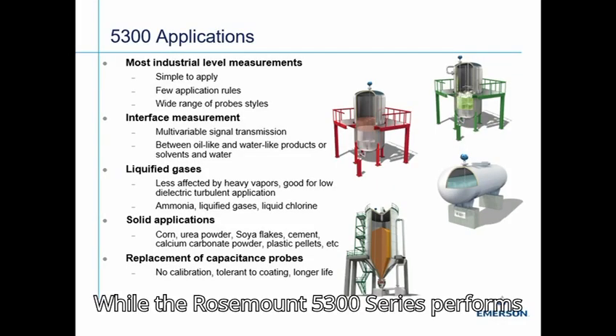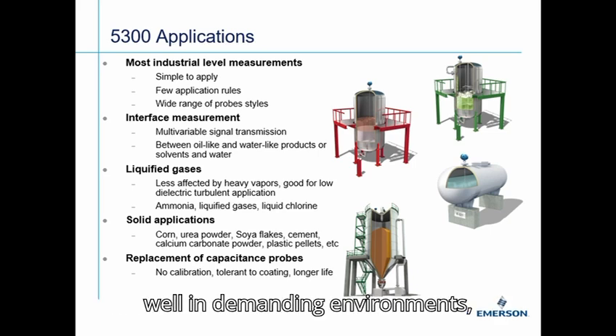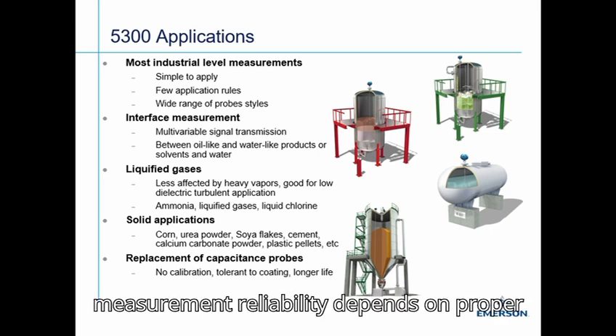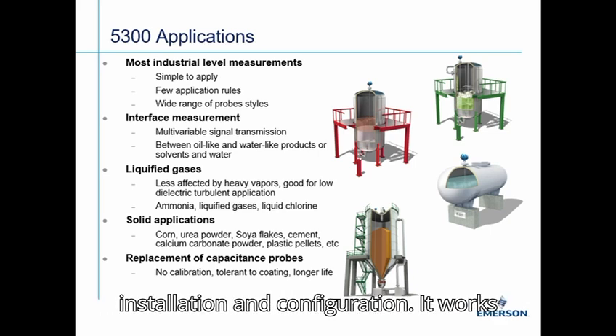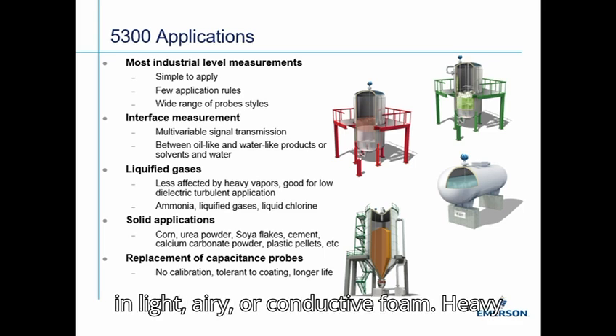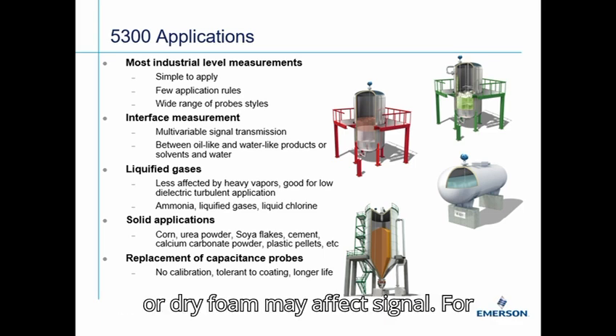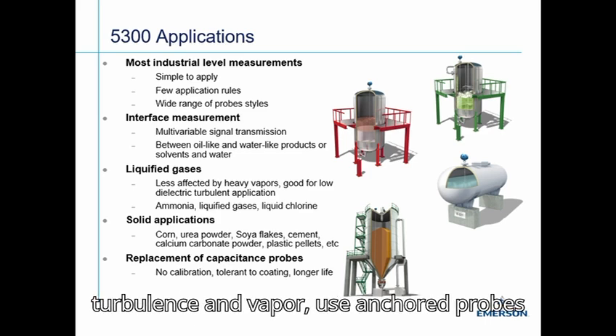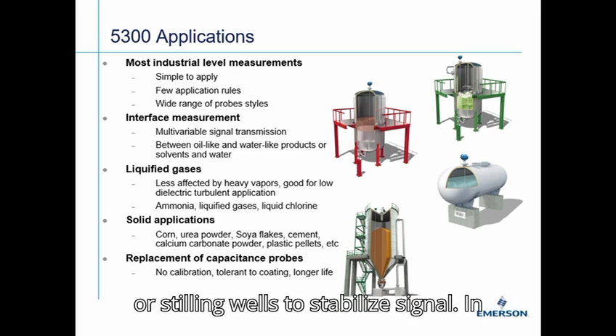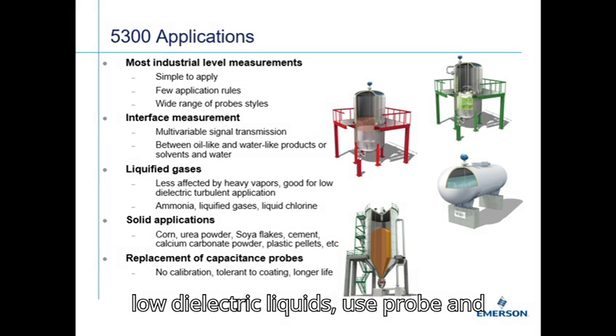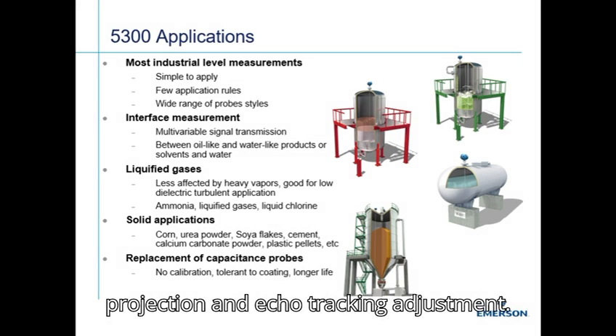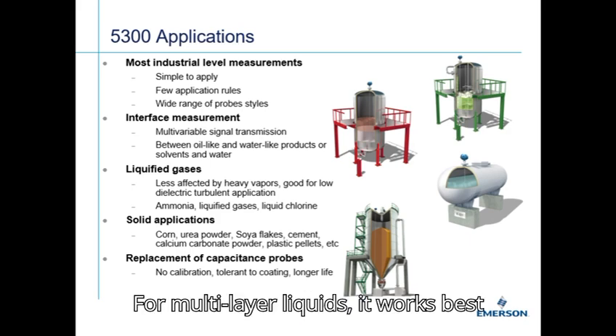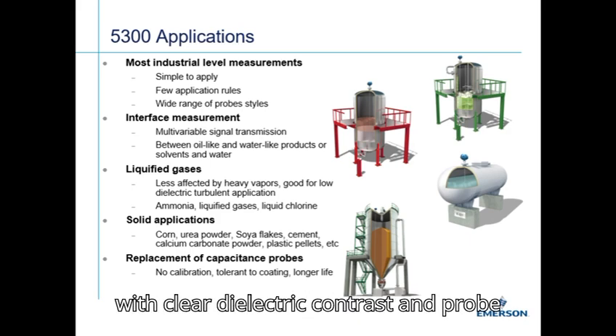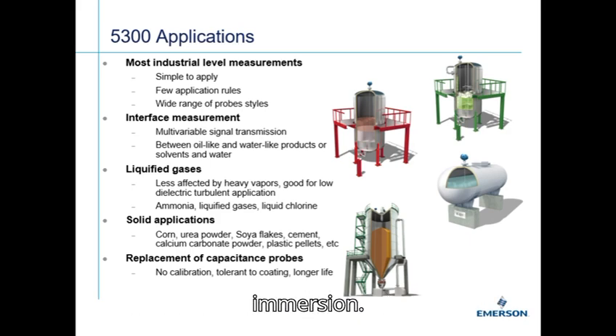While the Rosemount 5300 series performs well in demanding environments, measurement reliability depends on proper installation and configuration. It works in light, airy, or conductive foam. Heavy or dry foam may affect the signal. For turbulence and vapor, use anchored probes or stilling wells to stabilize the signal. In low dielectric liquids, use probe end projection and echo tracking adjustment. For multilayer liquids, it works best with clear dielectric contrast and probe immersion.